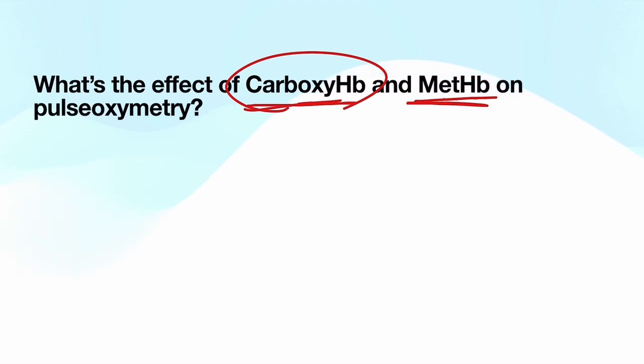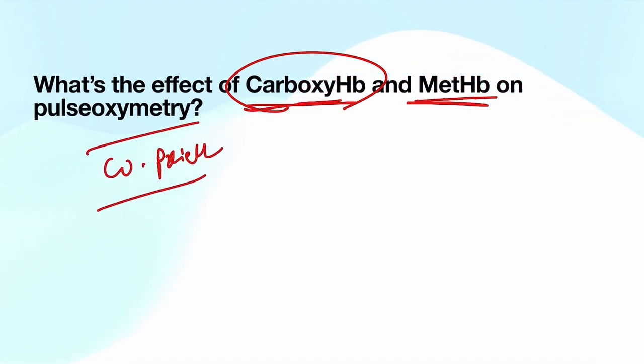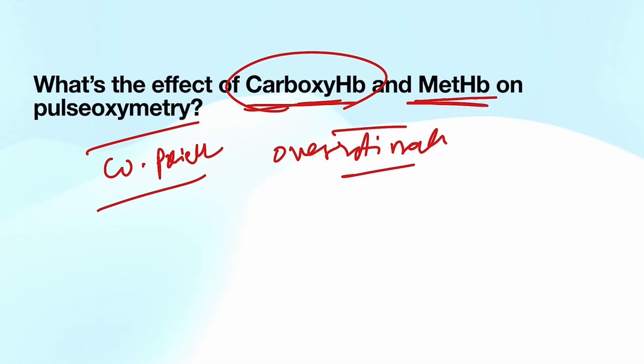Mostly in carbon monoxide poisoning, it overestimates the normal value. So what happens? Carboxyhemoglobin has a similar absorption spectrum as oxyhemoglobin. So it senses the carboxyhemoglobin as if it were oxyhemoglobin.